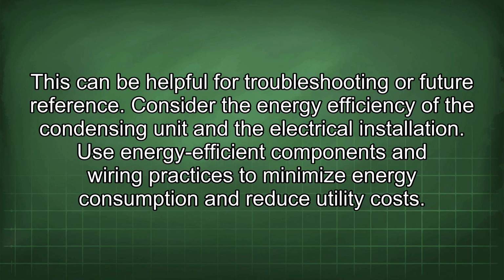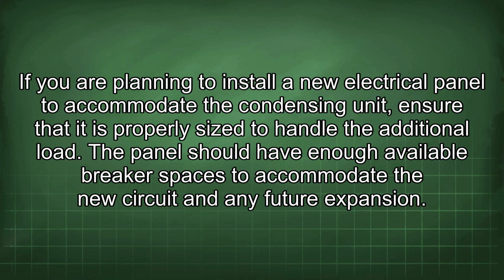Consider the energy efficiency of the condensing unit and the electrical installation. Use energy-efficient components and wiring practices to minimize energy consumption and reduce utility costs. If you are planning to install a new electrical panel to accommodate the condensing unit, ensure that it is properly sized to handle the additional load. The panel should have enough available breaker spaces to accommodate the new circuit and any future expansion.